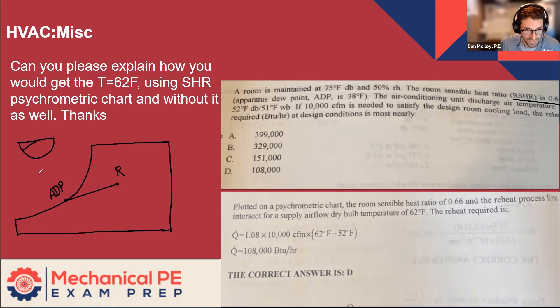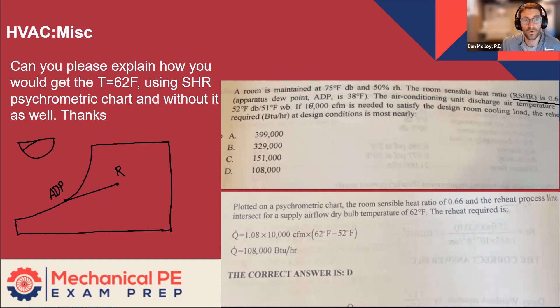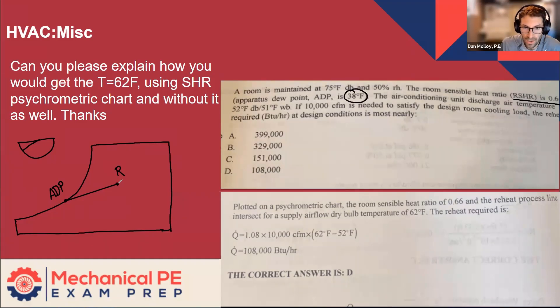With the computer-based test, there's no way of doing that. You could draw a series of parallel lines, but that sounds like an uphill battle. This problem is actually over-specified — they've given you the SHR and told you that the ADP is 38. So it's also true that if you start from the room condition and point directly at the ADP, by definition you're following the room sensible heat ratio.